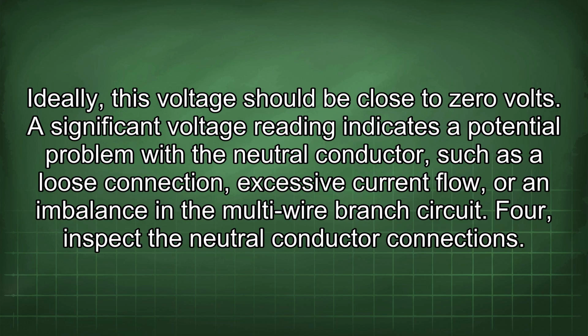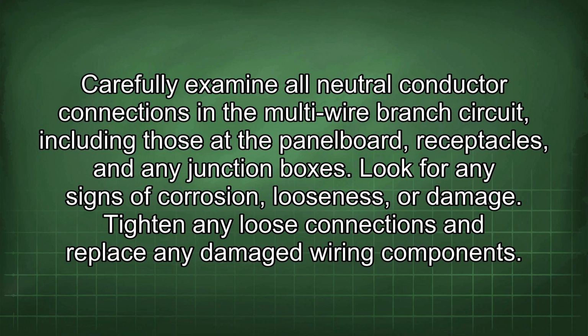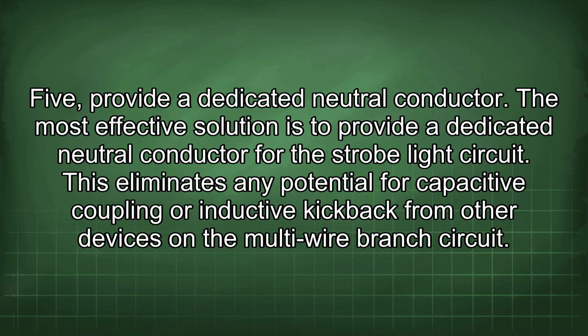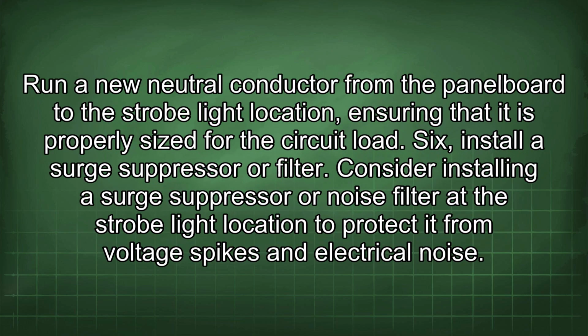4. Inspect the neutral conductor connections. Carefully examine all neutral conductor connections in the multi-wire branch circuit, including those at the panel board, receptacles, and any junction boxes. Look for any signs of corrosion, looseness, or damage. Tighten any loose connections and replace any damaged wiring components. 5. Provide a dedicated neutral conductor. The most effective solution is to provide a dedicated neutral conductor for the strobe light circuit. This eliminates any potential for capacitive coupling or inductive kickback from other devices in the multi-wire branch circuit. Run a new neutral conductor from the panel board to the strobe light location, ensuring that it is properly sized for the circuit load.